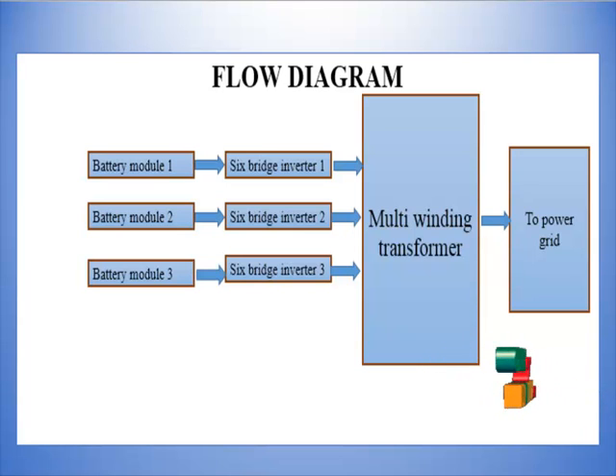A reconfigurable battery energy storage system is designed in such a way that the failure of individual battery modules will not cause the whole battery energy storage system to shut down. It consists of energy storage blocks, that means battery modules, DC to AC power electronic converter modules, and a multi-winding power transformer. The multi-winding transformer is used to integrate all the battery modules, which also enables the independent operation of each battery module. Each battery block in the reconfigurable battery energy storage system is controlled by its individual converter module. To quantify the C-rate related failure rates of power electronic converter components, note that the power losses of a power electronic converter are mainly the power losses in the IGBTs and diodes.